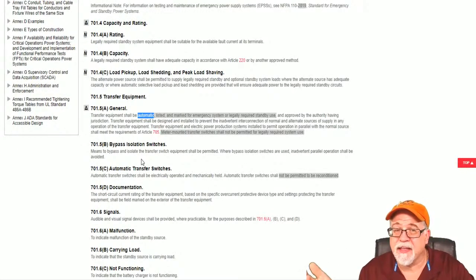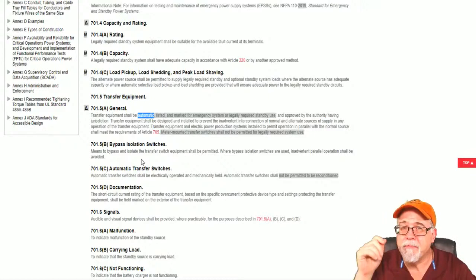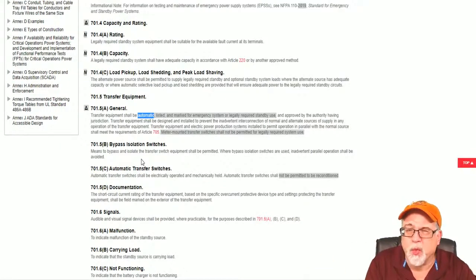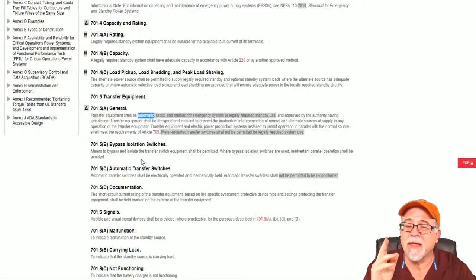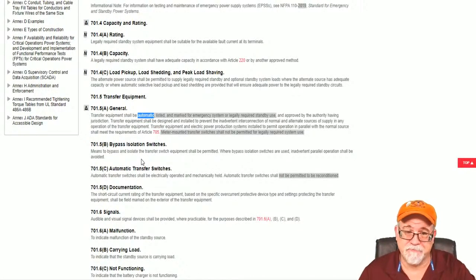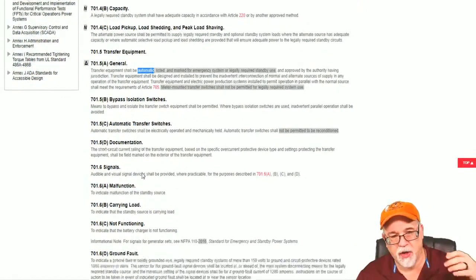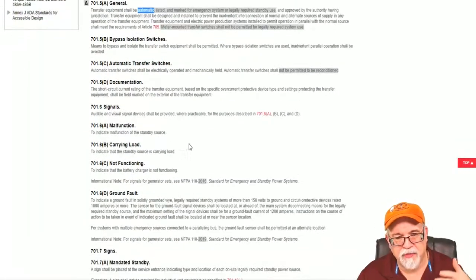Whereas the optional method in 702, that's manual. Can it be automatic? Sure, if you want, but it's allowed to be manual. Whereas the legally required or emergency system has to be automatic transfer. And then, of course, you've got all these other requirements of the load that's got to be transferred.